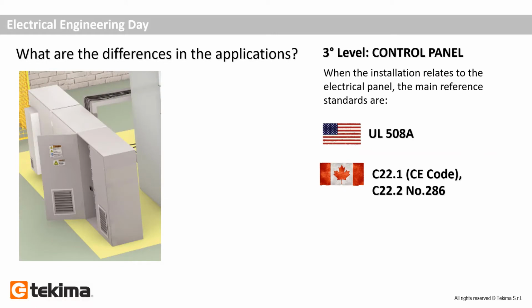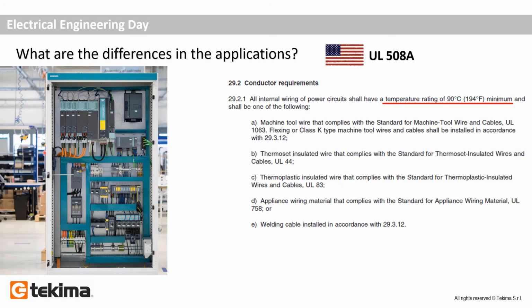In the control panels, again, one main standard, UL 508A for the USA, and two standards, C22.1 and C22.2 number 286 for Canada. What is the requirement for cable inside the panels? Minimum temperature rating of 90 degrees.